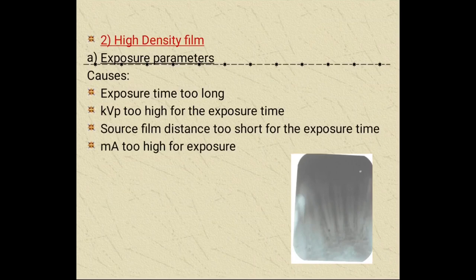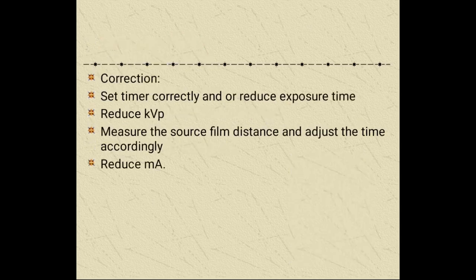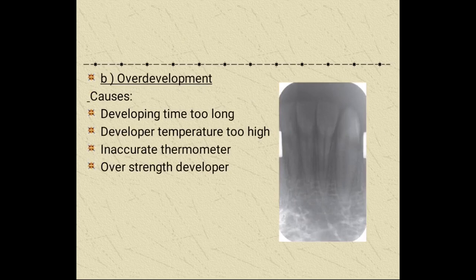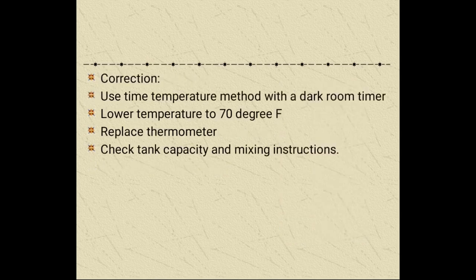A high density film is caused by exposure time being too long, kVp too high for the exposure time, or source-film distance too short for the exposure time. Correction involves setting the timer correctly or reducing exposure time, reducing kVp, measuring the source-film distance and adjusting accordingly, and reducing milliampere. Over-development is caused by developing time too long, developer temperature too high, inaccurate thermometer, or over-strength developer. Correct by using the time-temperature method with a darkroom timer, lowering temperature to 70 degrees Fahrenheit, replacing the thermometer, and checking tank capacity and mixing instructions.